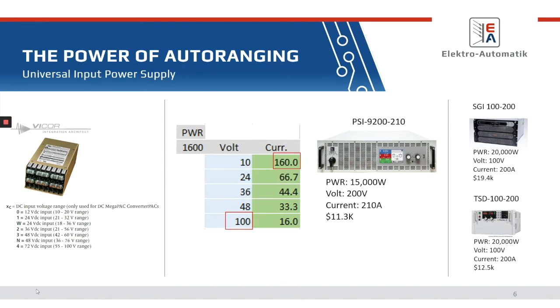Also, we talked about planning for the future. We doubled the voltage. The auto ranging power supply gives you that ability to say, hey, I know I only need 100 now, but what if I need to test at 110 volts or 115 volts in the future? Hey, I can get a 200 volt auto ranging power supply, still covers my application at 100 volts. I'm good to go. And if you look over on the right, the other models, you're at 100 volts, 200 amps. So the auto ranging power supply is providing 10 more amps and is also a more cost-effective solution and is also half the size. The 20 kilowatt power supplies you see on the right are a 6U chassis versus a standard 3U chassis.